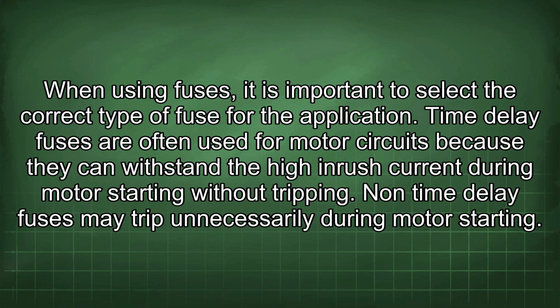When using fuses, it is important to select the correct type of fuse for the application. Time delay fuses are often used for motor circuits because they can withstand the high inrush current during motor starting without tripping. Non-time delay fuses may trip unnecessarily during motor starting.